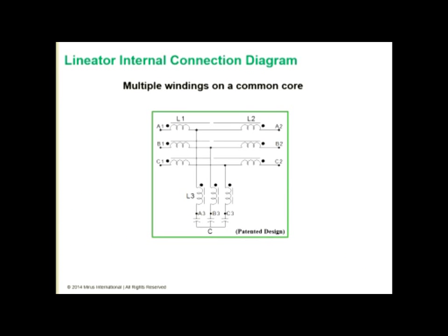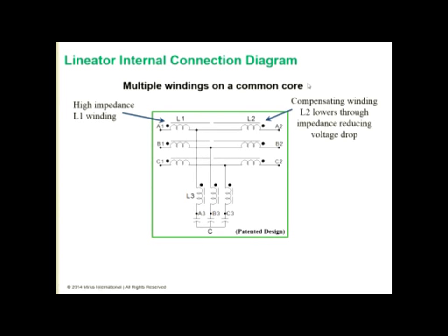So this slide shows the basic connection diagram for a filter. There is an input blocking reactor, three-phase input blocking reactor that provides high impedance on the input to the filter. There's an output reactance on the same common core that compensates and reduces the voltage drops and improves performance. This combination of reactance allows us to design the filter with much lower capacitive reactive power, and there is a tuned branch circuit with the reactor and the capacitors.